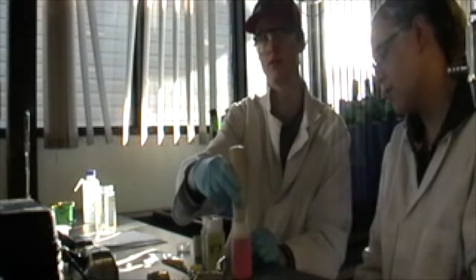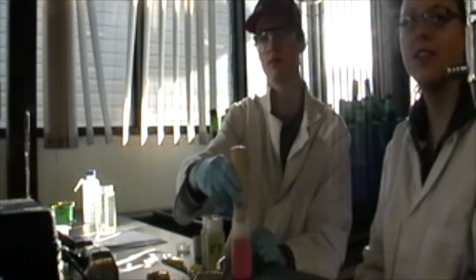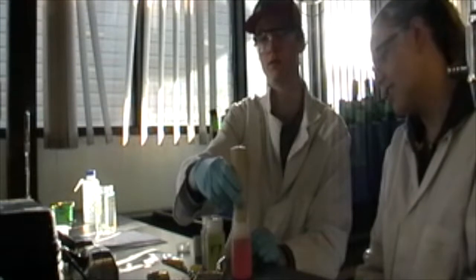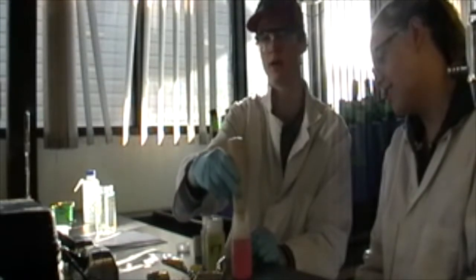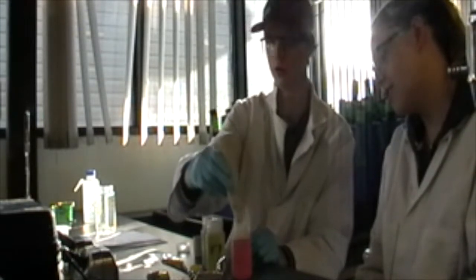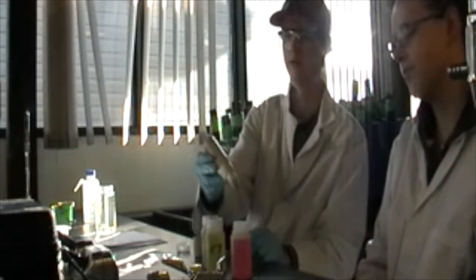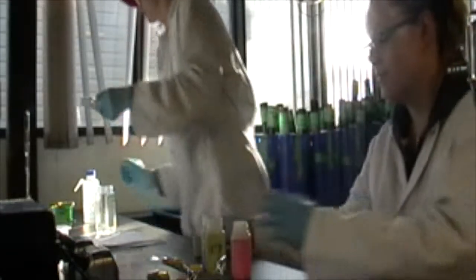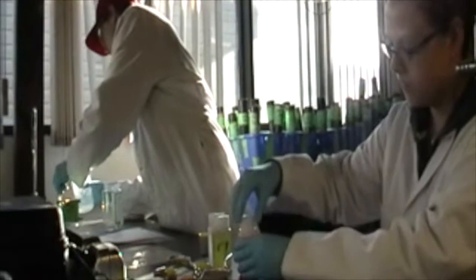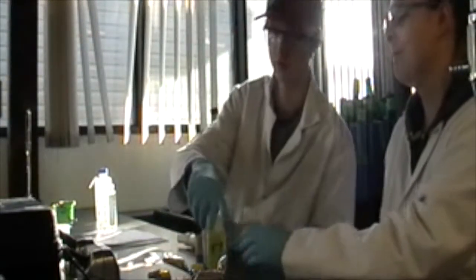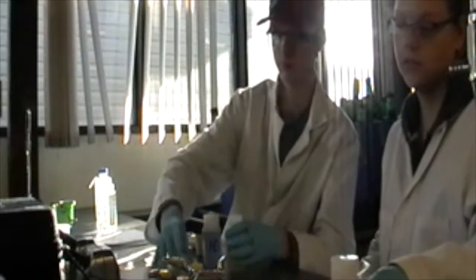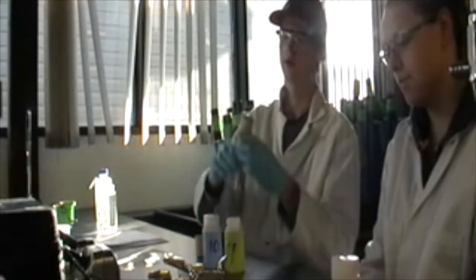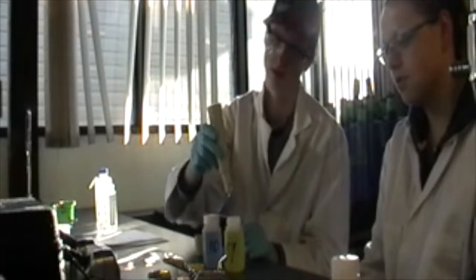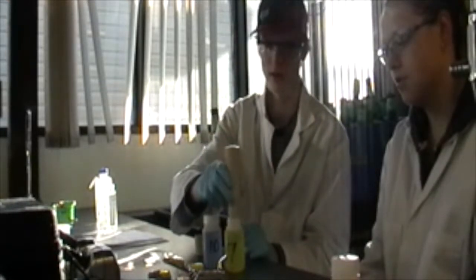Is that 4? We are. Now it's calibrated for the pH of 4. But before going to number 7, we're going to rinse with distilled water. Again, we're going to put our probe into the pH of 7 and hit calibrate.